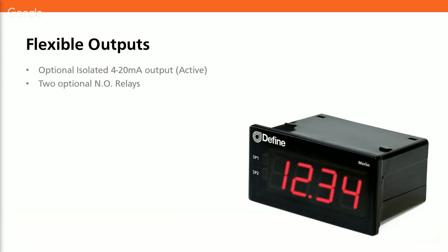The output mirrors the value that is shown on the display, and it can be rescaled to anything that you like. So for example, you can set it so that when the display shows 0, the output is 4 milliamps, and when the display shows 100, the output is 20 milliamps. Or conversely, you could set it so it's 4 milliamps when the display shows 100 and 20 when that's 0, or any other combination you can think of.